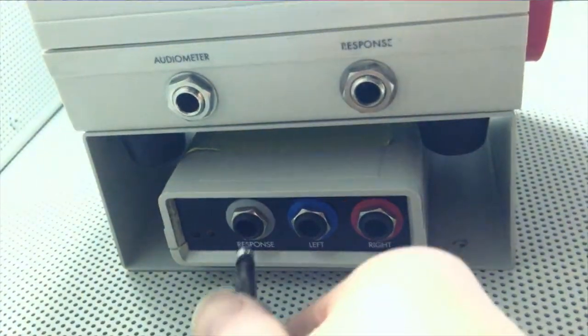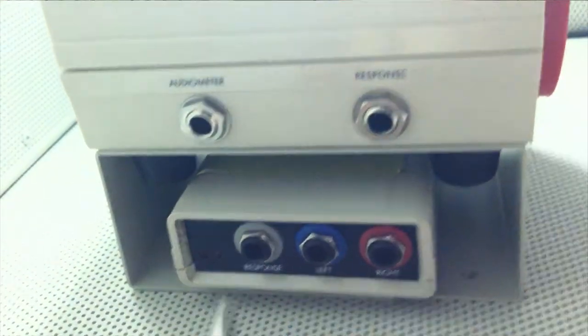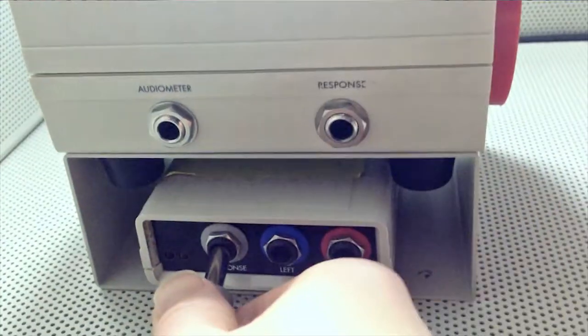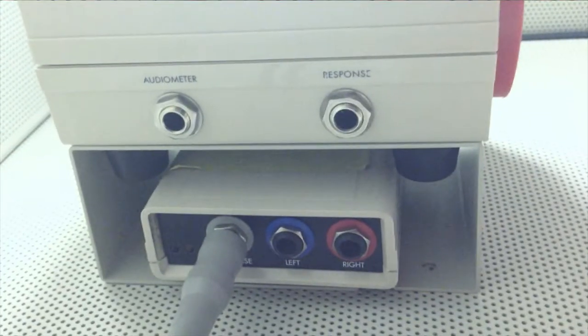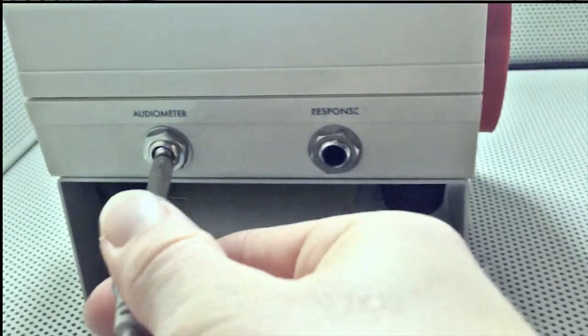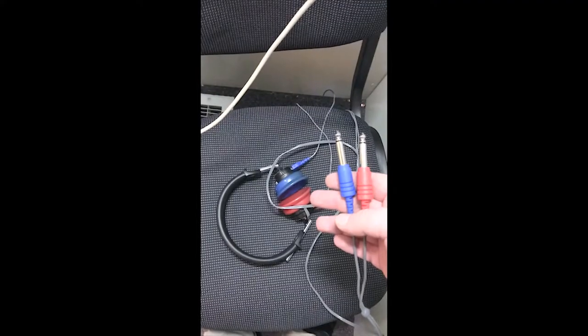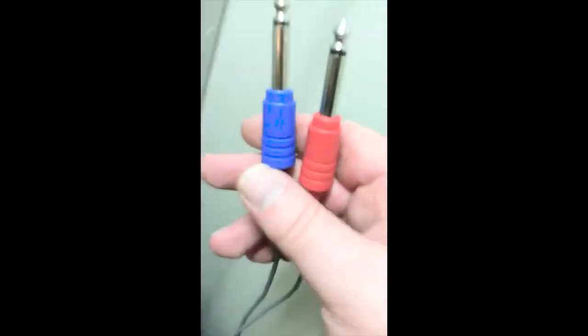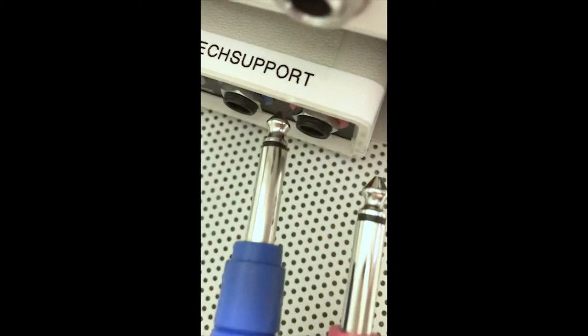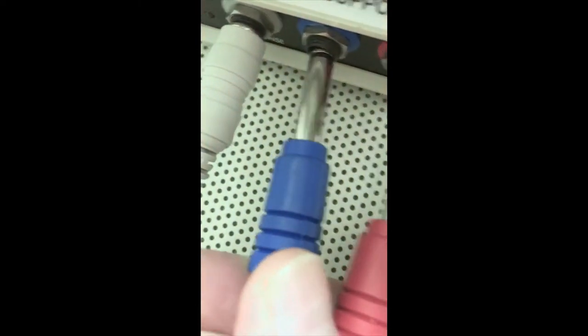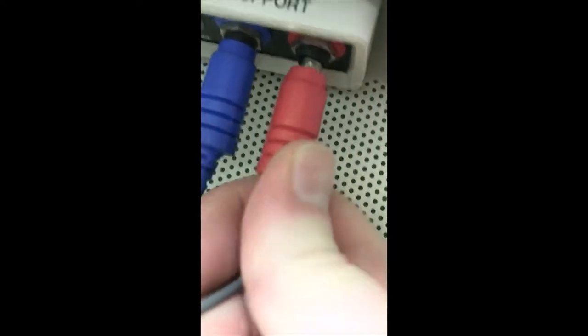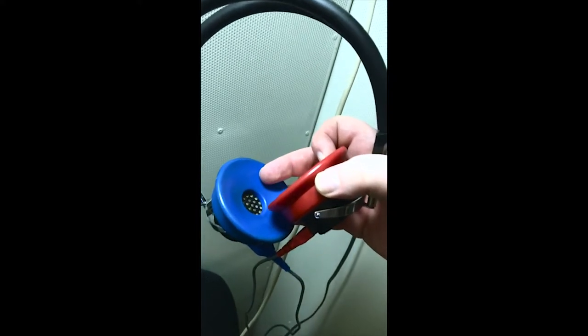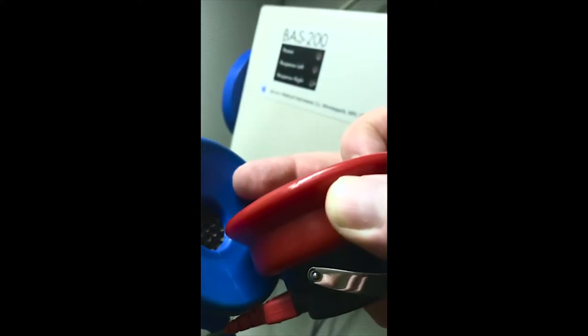And then you take your patch cable and plug it into the response input of the CCA-200 mini and plug the other end into the audiometer portion. Then take your headset plugs, plug them in from blue to blue and red to red, or blue to left and red to right. Then you take the headset portion and put it on the ear cuffs of the BAS-200.